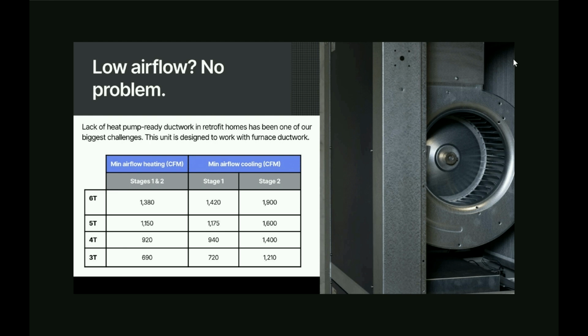One of the other challenges was ductwork, retrofit ductwork, right? These are houses that were never thought about with a heat pump in mind, right? We were never thinking about providing that size of ductwork so that we could be warm and comfortable in our houses. And we wanted to basically make something that behaved a little bit more like a furnace and can operate at lower airflows. So we're able to push out 100% of the heat that we need as low as 230 CFM per ton. When you set the airflow for heating and cooling on the control board, in the event that second stage cooling needs to be locked out, it just automatically does so. And that's really how we're able to push more heat on the heating side.